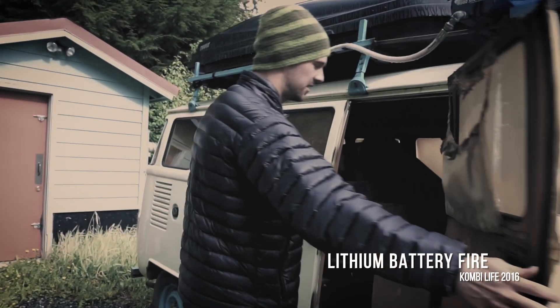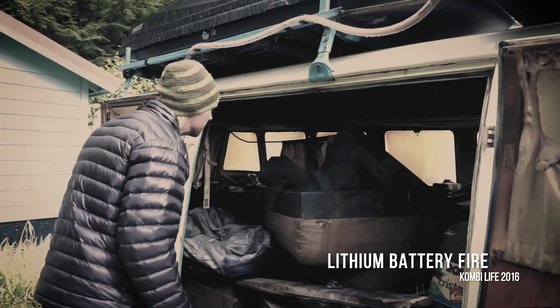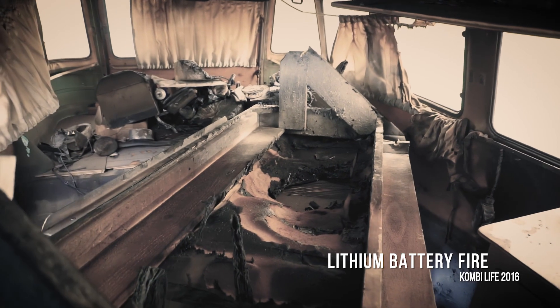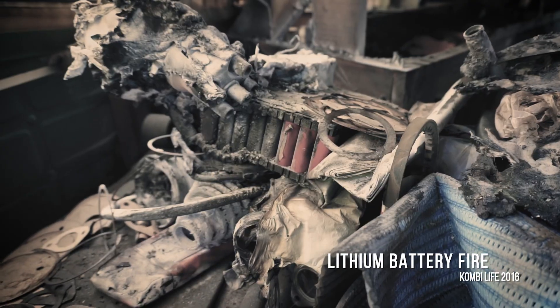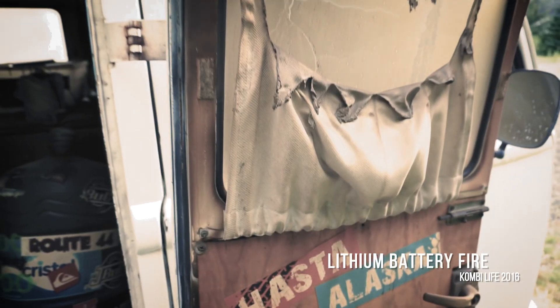The basic problem with lithium-ion batteries in general is that there's a liquid electrolyte, and that liquid electrolyte when combined with oxygen can be flammable. When you get oxygen produced inside the cell because it gets very hot, that produces a condition known as thermal runaway — and that's bad. That's when you get fires started, which could be caused by an internal short circuit or charging at too high a voltage.